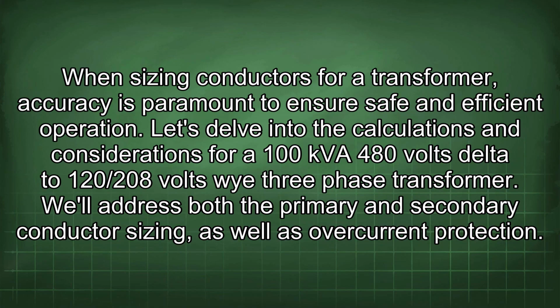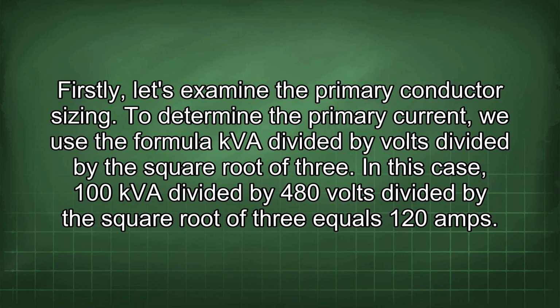When sizing conductors for a transformer, accuracy is paramount to ensure safe and efficient operation. Let's delve into the calculations and considerations for a 100 kVA 480 volts delta to 120/208 volts Y three-phase transformer. We'll address both the primary and secondary conductor sizing, as well as overcurrent protection. Firstly, let's examine the primary conductor sizing.